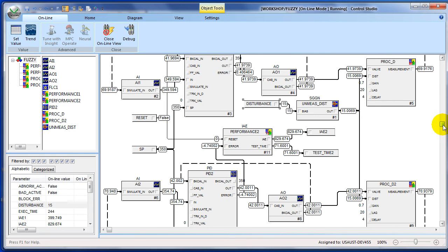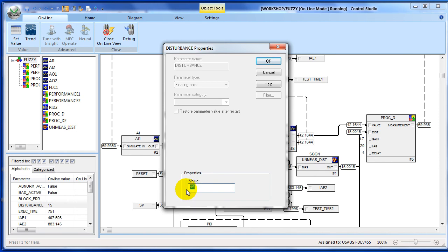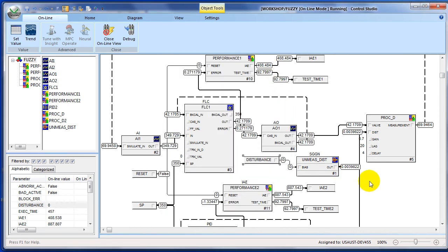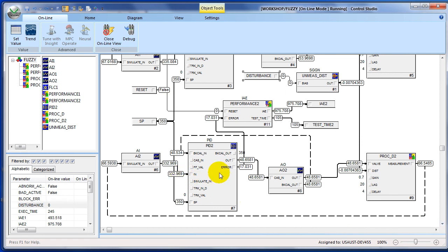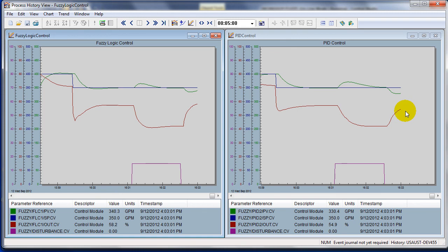In this particular case, if we compare them, the integral of absolute error is dramatically different for fuzzy logic control than for PID control. The amount of improvement for disturbance rejection is based upon the dynamics of your process. On this lag-dominated process, the improvement is fairly dramatic. When we reduce the disturbance again, we notice that the PID is slower in responding. The trend shows that the fuzzy logic control is taking much more abrupt action due to the nonlinear behavior of fuzzy, which means we get back to set point much faster with fuzzy logic control than with PID.